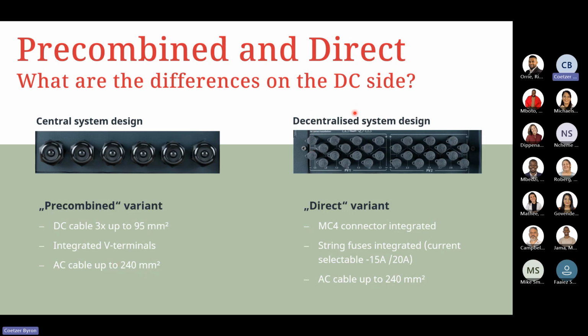Whereas on the decentralized system design, the direct variant, we'll have integrated MC4 connector points at the bottom, and we have string fuses that are also integrated on the inboard DC boards located inside the unit itself. We have different amperages for the fuses. We can have 15 or 20 amp fuses on the board itself to accommodate if we're using larger modules, so we can change these fuses. Again, your AC cable connection points of up to 240 mm² come into the unit on the AC side.